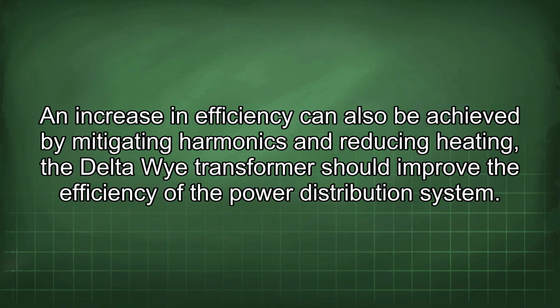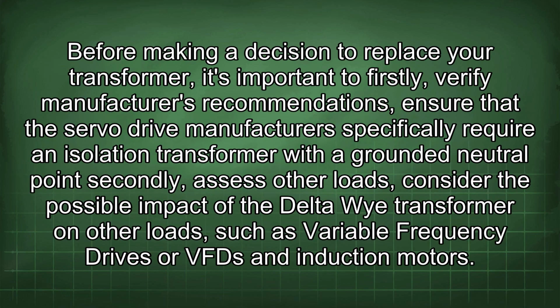An increase in efficiency can also be achieved by mitigating harmonics and reducing heating. The Delta Wye transformer should improve the efficiency of the power distribution system. Before making a decision to replace your transformer, it's important to firstly verify manufacturer's recommendations. Ensure that the servo drive manufacturers specifically require an isolation transformer with a grounded neutral point.